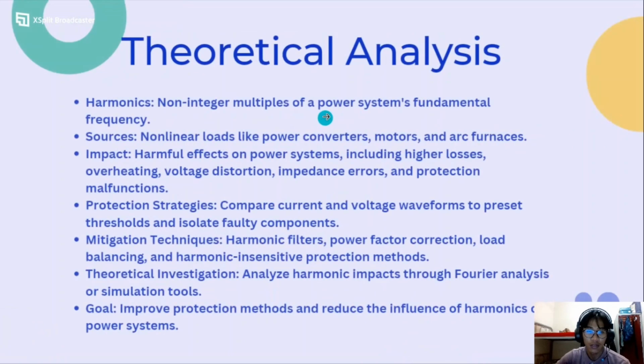The first part is theoretical analysis. Harmonics are integer multiples of a power system's fundamental frequency. The sources are nonlinear loads like power converters, motors, and arc furnaces. The impact of harmonics is harmful effects on the power system, including higher losses, overheating, voltage distortion, impedance error, and protection malfunction. The protection strategy is to compare current and voltage waveforms to preset thresholds and isolate the faulty component. The mitigation techniques are harmonic filters, power factor correction, load balancing, and harmonic insensitive protection methods. For the theoretical investigation, we analyze harmonic impacts through Fourier analysis or simulation tools. The goal is to improve protection methods and reduce the influence of harmonics on the power system.